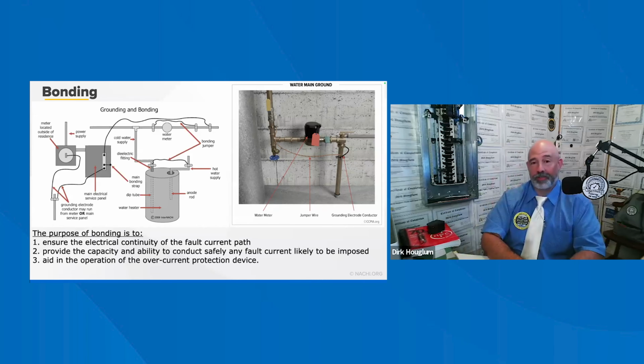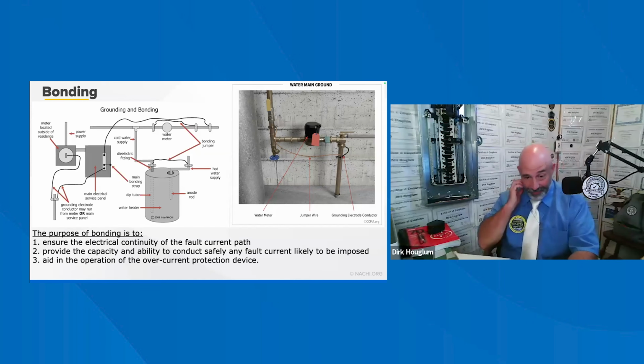I just butchered that whole sentence, didn't I? Inspectors may observe some of those water lines bonded at the water heater supply pipe and the metal gas pipe that are as close to the panel board as possible. For a 200 amp service, the code calls for at least 6 gauge copper to bond metal gas pipes and 4 gauge copper for water pipes. Yeah, sorry about that.